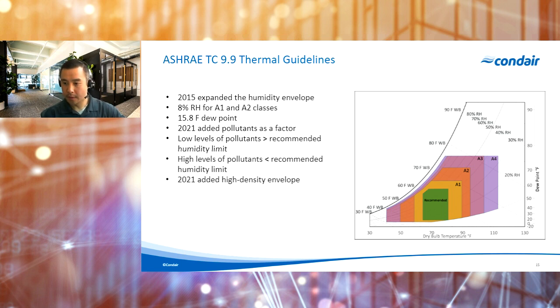Sure. So let me see. I would recommend that anyone that does work in this field get themselves a copy of Thermal Guidelines for Data Processing Environments. It's a very, very good document. There's also some free handouts. So the recommended range right now, what's in green, dry bulb is 64.4 to 80.6 degrees Fahrenheit. The upper range is either 70 or 50% relative humidity. In the most recent release, there have been some stipulations of upper relative humidity based on corrosion potential in the air. So if your air is a little bit more corrosive, then it's a slightly lower recommended relative humidity.